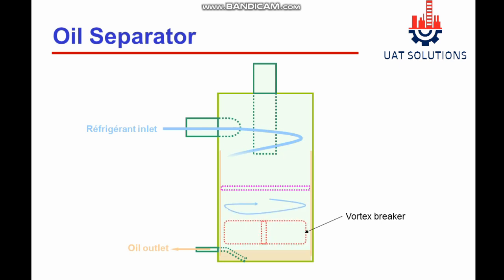The oil leaves the sump through the side of the separator via a pickup tube. This tube is bent at an angle to remove oil from the bottom of the sump. After the oil leaves the sump, it is returned to the compressor where it enters the motor rotor housing. Differential pressure between the sump and the compressor suction drives the flow of oil.